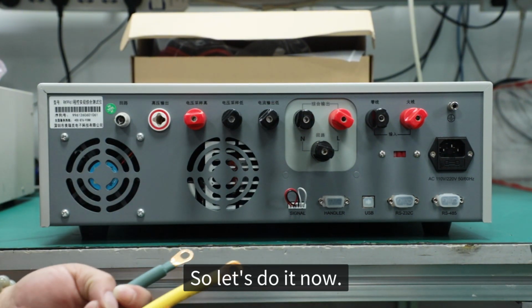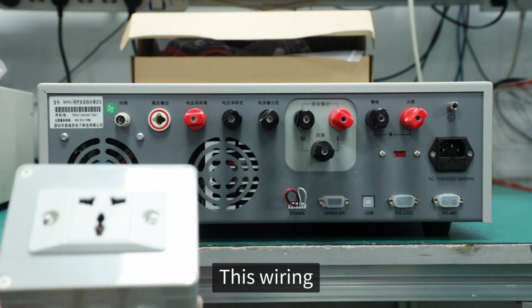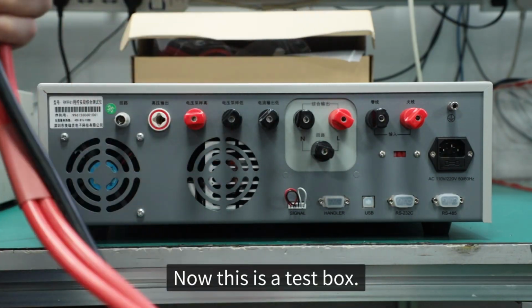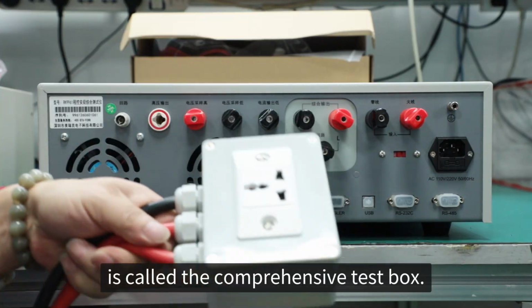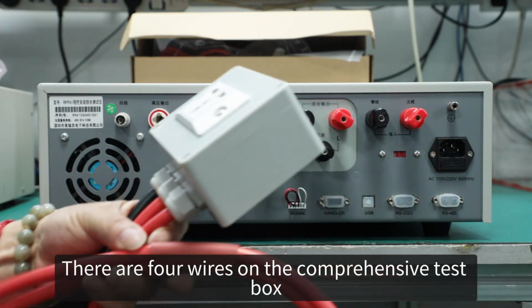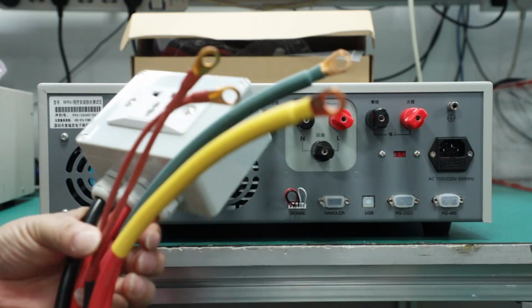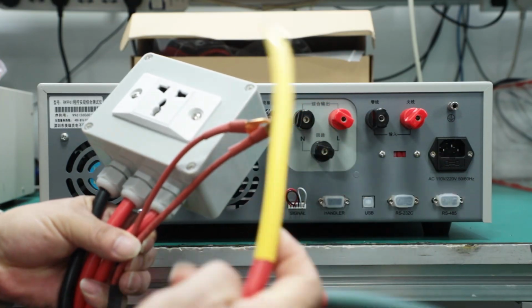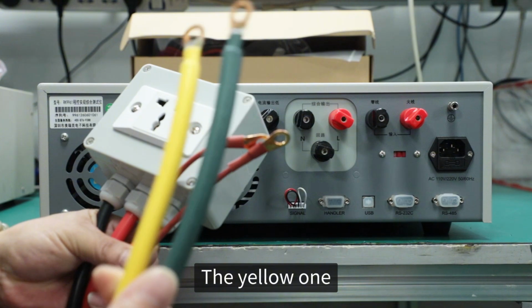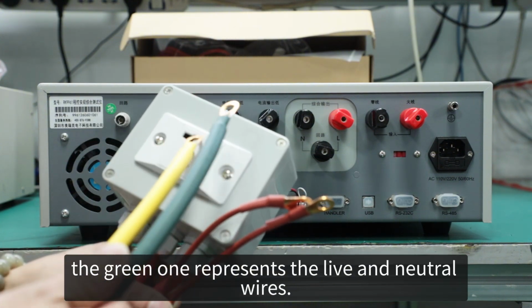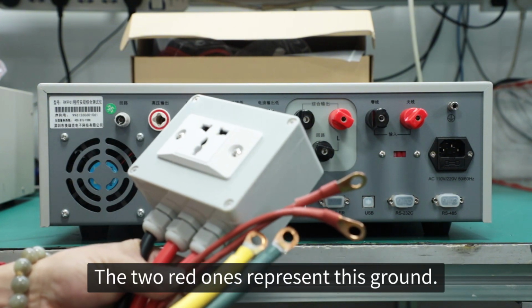So let's do it now. This wiring. Now this is a test box, called the comprehensive test box. There are 4 wires on the comprehensive test box. These 4 wires: the yellow one and the green one represent the live and neutral wires. The 2 red ones represent the ground.